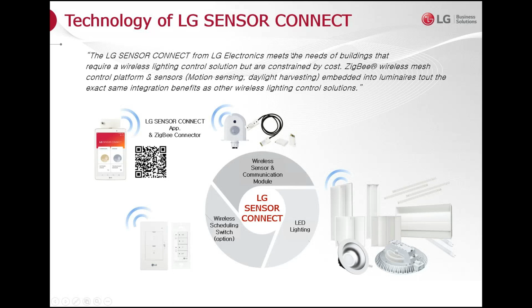For the technology that we use, once again, we're using Zigbee Wireless. For those of you that are not aware, Zigbee is a wireless protocol that runs on the 2.4 gigahertz spectrum. The way we use Zigbee is we have an app that runs on Android only. The reason for that is that we've also manufactured a Zigbee USB antenna. This USB antenna plugs directly into the Android device. That means that the Android device is communicating directly with the wireless modules in the light. The wireless module being either a dongle, which is just a wireless chip and nothing else, which contains light levels, or a sensor, which is a dongle with a wire attached to a sensor that's got a photocell for daylight and a PIR sensor for motion.